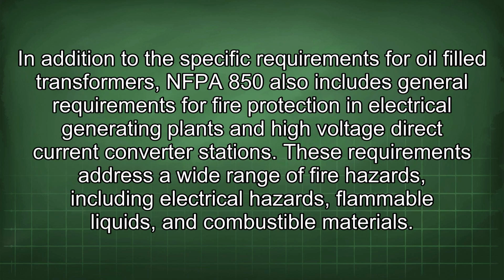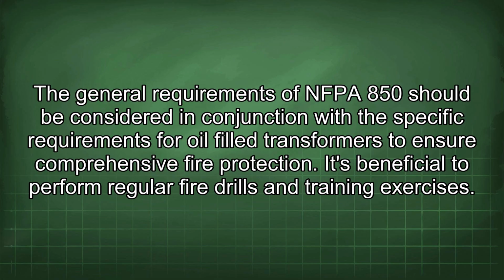In addition to the specific requirements for oil-filled transformers, NFPA 850 also includes general requirements for fire protection in electrical generating plants and high-voltage direct current converter stations. These requirements address a wide range of fire hazards, including electrical hazards, flammable liquids, and combustible materials. The general requirements of NFPA 850 should be considered in conjunction with the specific requirements for oil-filled transformers to ensure comprehensive fire protection.